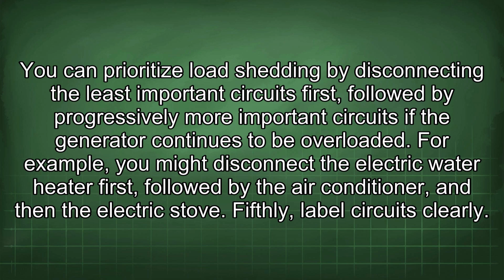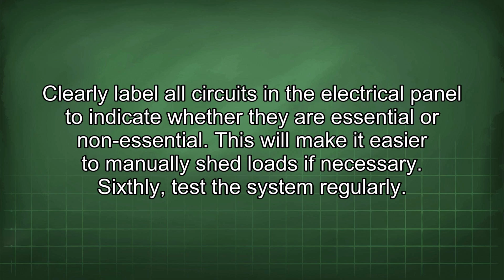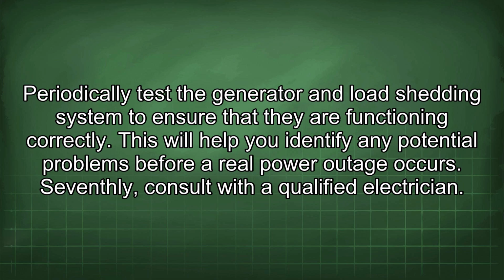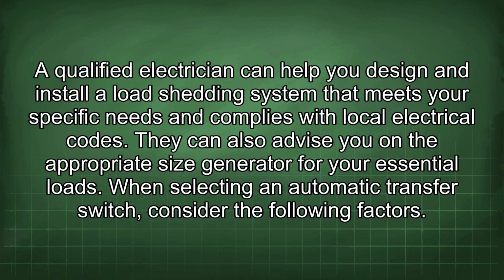Fifthly, label circuits clearly. Clearly label all circuits in the electrical panel to indicate whether they are essential or non-essential. This will make it easier to manually shed loads if necessary. Sixthly, test the system regularly. Periodically test the generator and load shedding system to ensure that they are functioning correctly. This will help you identify any potential problems before a real power outage occurs. Seventhly, consult with a qualified electrician. A qualified electrician can help you design and install a load shedding system that meets your specific needs and complies with local electrical codes. They can also advise you on the appropriate size generator for your essential loads.